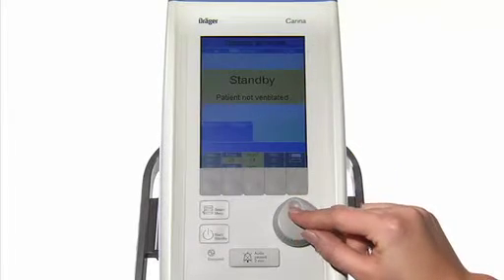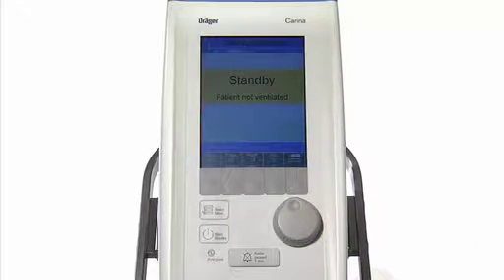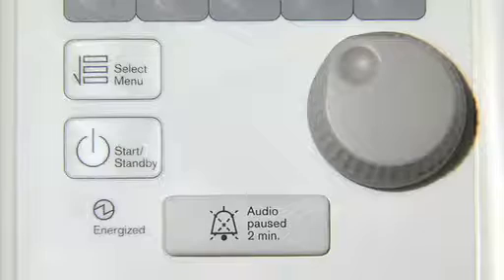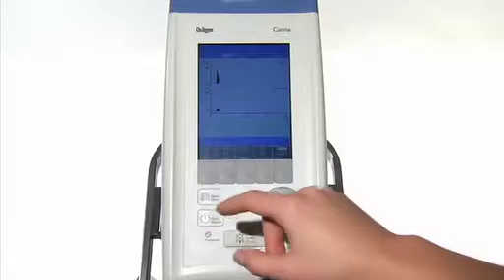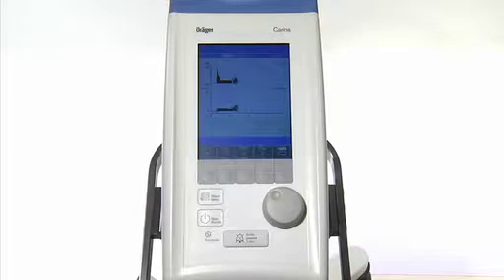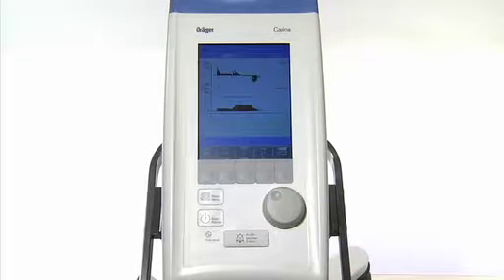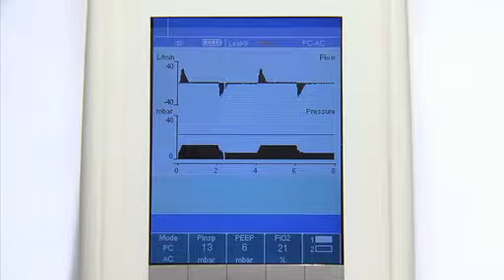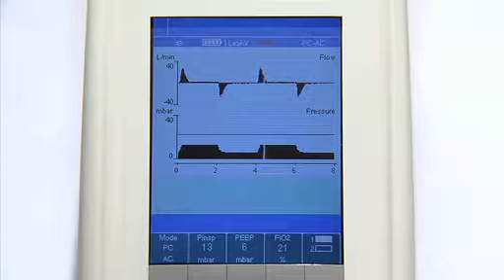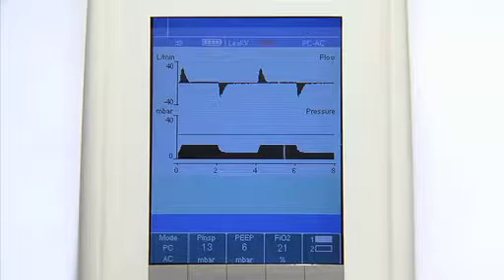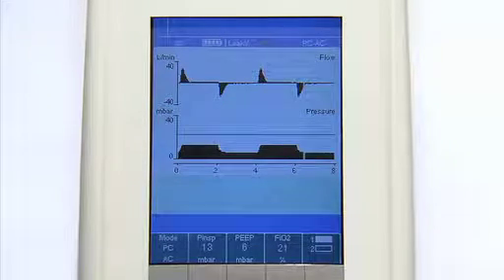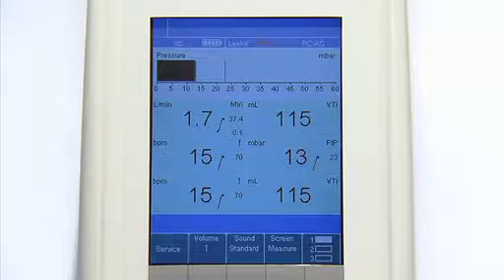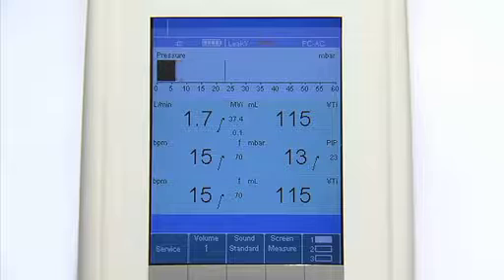Once you have chosen the setting, press the rotary knob to activate your selection. Ventilation can be started or stopped by pressing the Start Standby button. Let's take a look at Carina's screen. To suit your individual needs, you can choose between different views, pressure and flow curve, or a bar chart view with values. Both can be configured fast and easily.